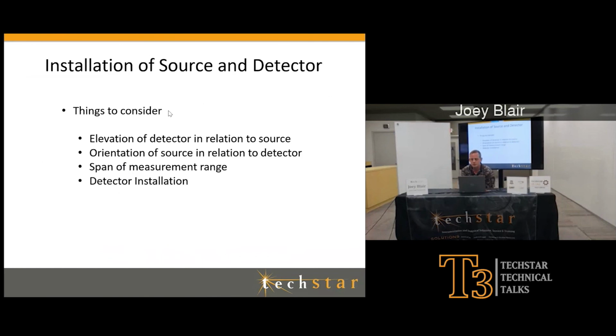So back to installation of the source and the detector. Things to consider: your elevation of the detector in relation to the source. We've talked about that several times. Orientation of the source in relation to the detector. We've talked about that as well. Your total span of your measuring range. How much do I want? What's my span going to be? Installation of your detector itself. How are we going to install it? Where are we going to install it? We need to get it in the center of that radiation field.